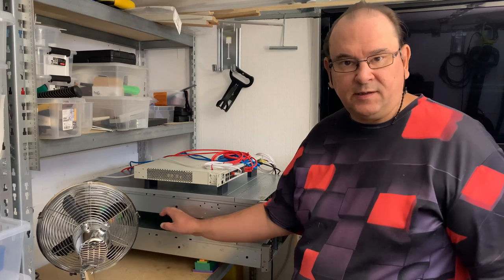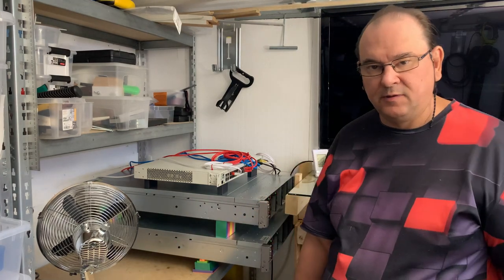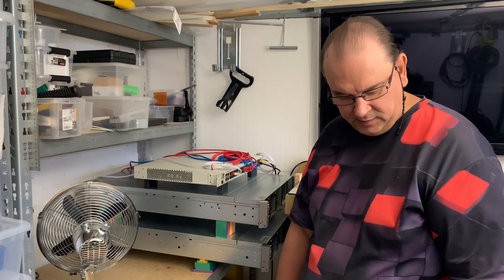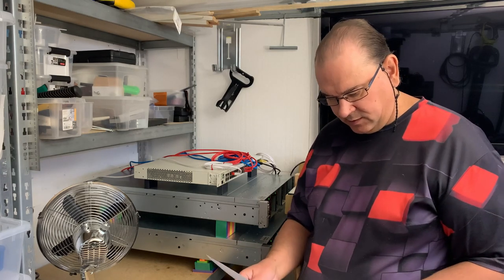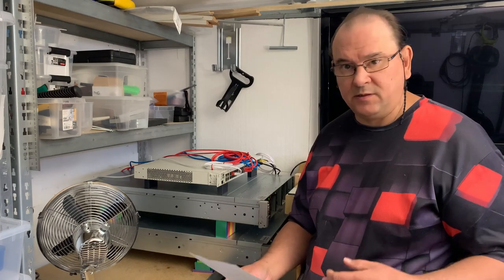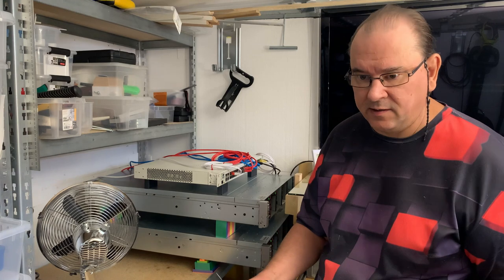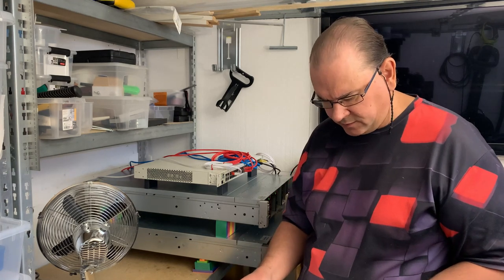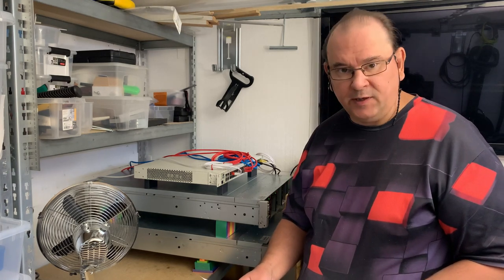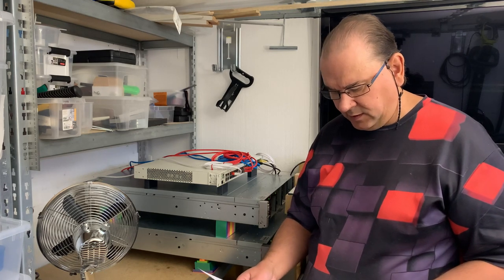There have been thermal shutdowns and I lost one hard drive because I let it go to a little bit extreme. So I made a little cheat sheet for this environment — this is for when you have more or less sunny conditions outside and it's summer conditions in our region. So if it's 20 Celsius outside, ambient...